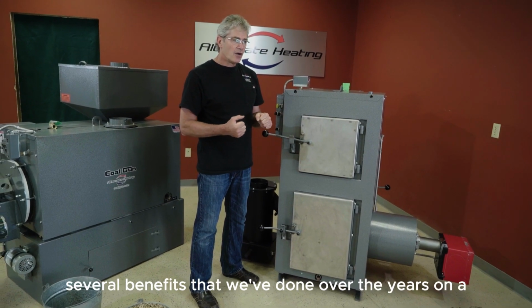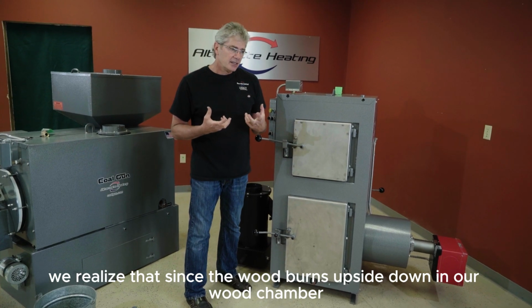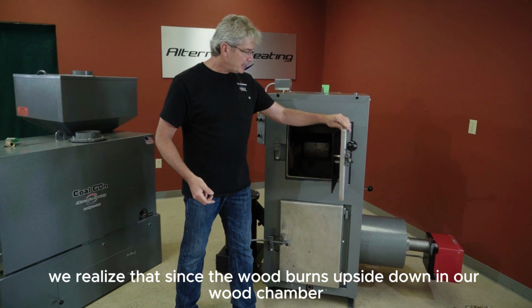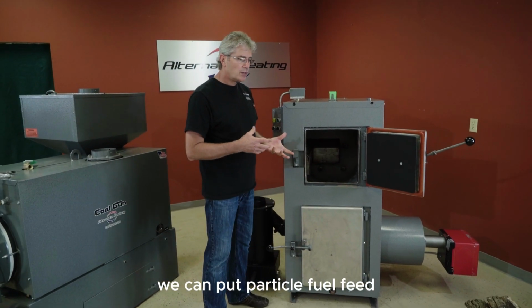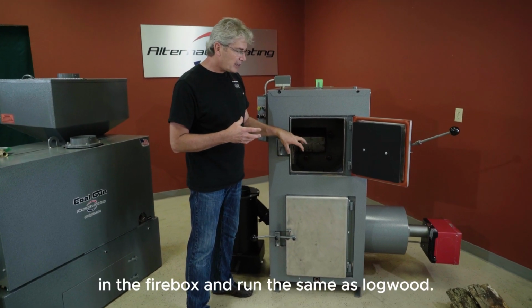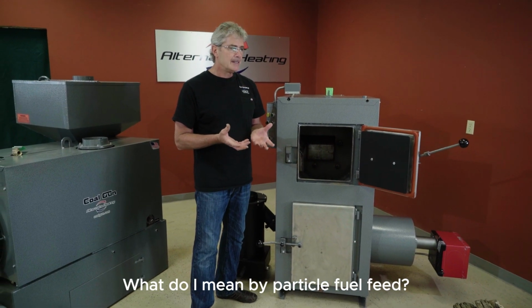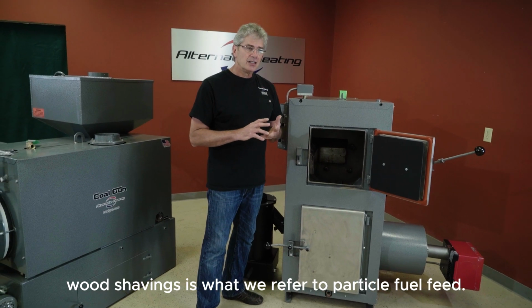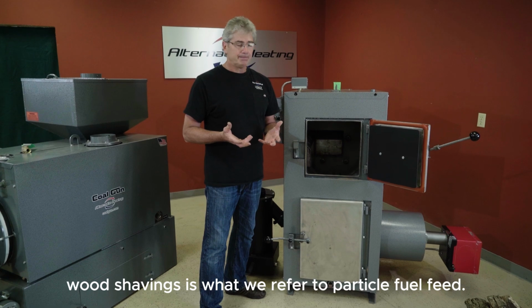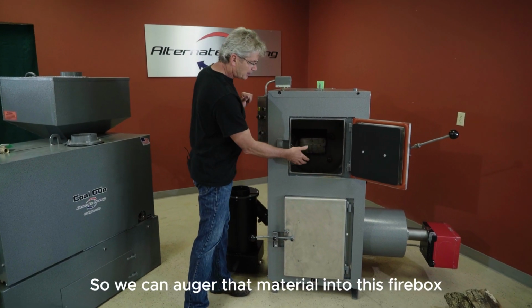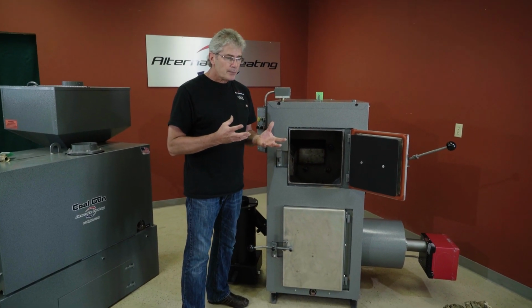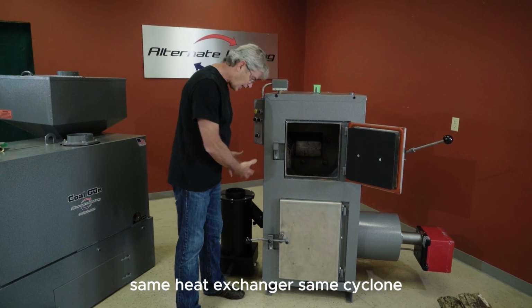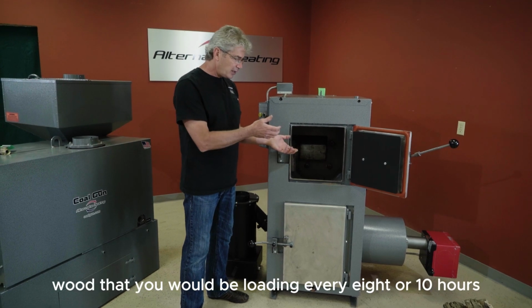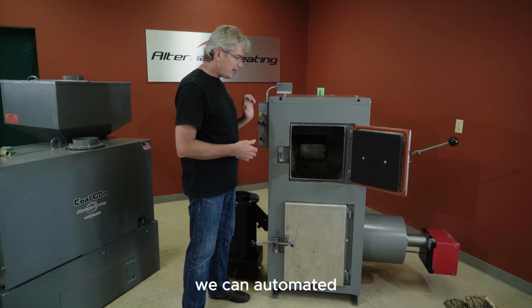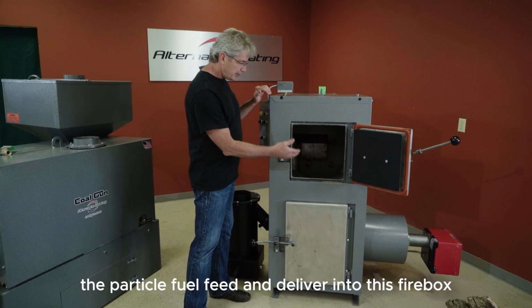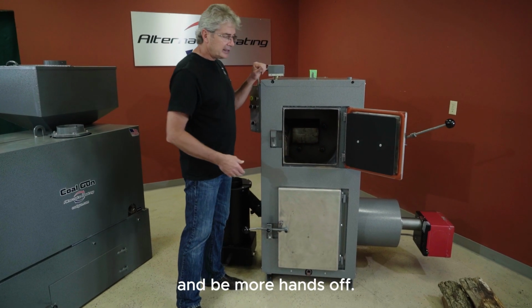Several benefits that we've added over the years on our wood gun: we realized that since the wood burns upside down in our wood chamber, we can put particle fuel feed in the firebox and run it the same as logwood. What do I mean by particle fuel feed? Sawdust, wood chips, wood shavings is what we refer to as particle fuel feed. So we can auger that material into this firebox and it burns very efficiently. It uses the same process, same refractory, same heat exchanger, same cyclone. But instead of using logwood that you would be loading every 8 or 10 hours, we can automate a system that we can auger the particle fuel feed and deliver into this firebox and be more hands-off.